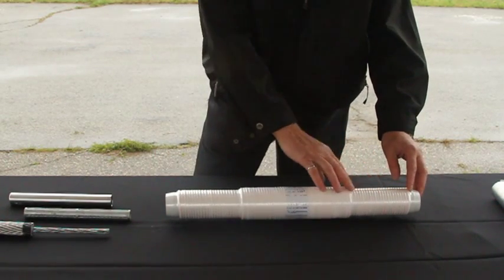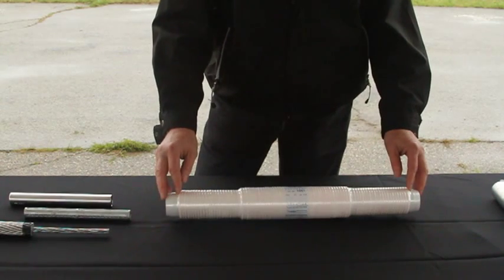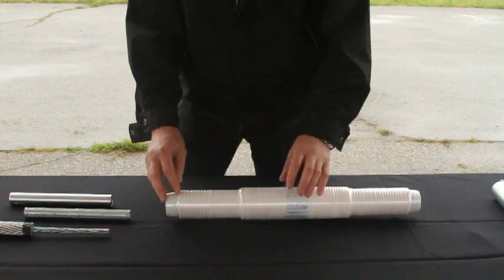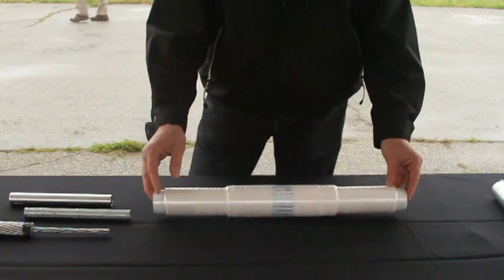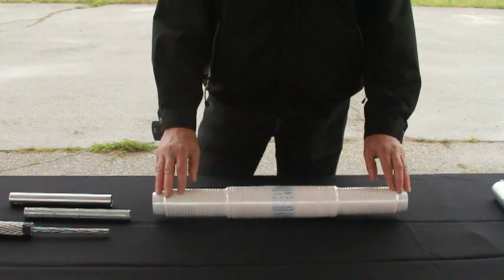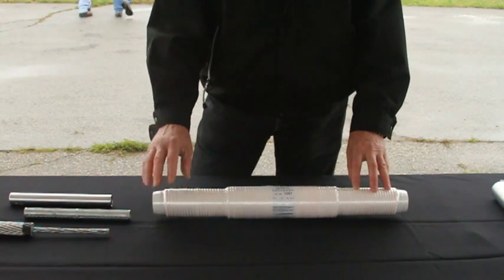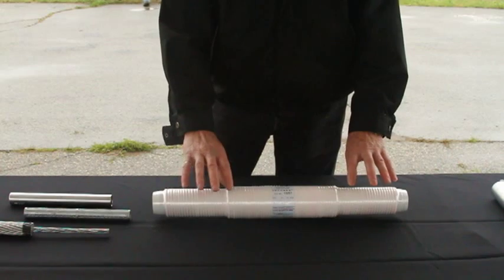As you can see, we have a cord which contains this explosive material, which is wrapped all along the sleeve. When this cord is detonated, the energy developed by this explosion is used to compress the sleeve, compress the steel, the conductor, and anything that's inside.